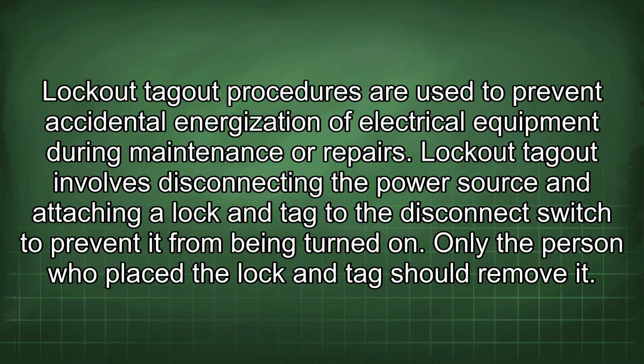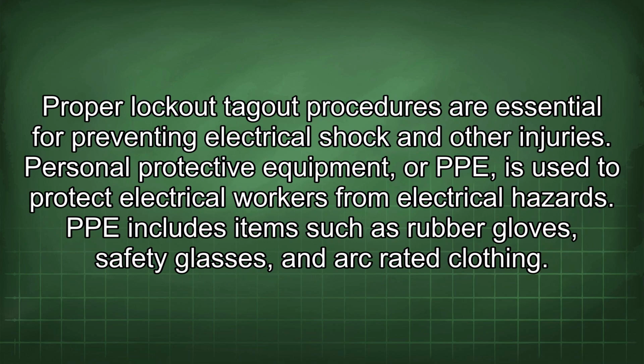Lockout-tagout procedures are used to prevent accidental energization of electrical equipment during maintenance or repairs. Lockout-tagout involves disconnecting the power source and attaching a lock and tag to the disconnect switch to prevent it from being turned on. Only the person who placed the lock and tag should remove it. Proper lockout-tagout procedures are essential for preventing electrical shock and other injuries.